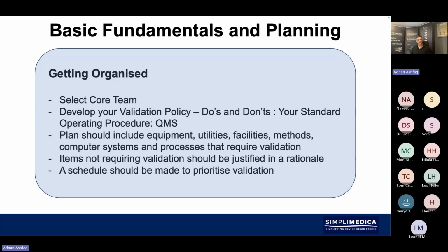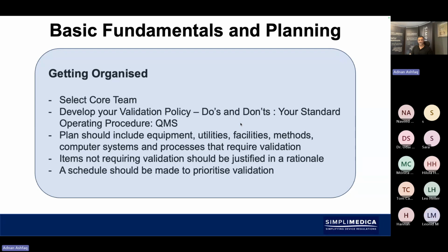How do you control the parameters and what parameters? What's the acceptance criteria? There have been occasions where I've had some vendors or clients tweaking the parameters as they're going along. This is very hard to validate because the whole premise of validation is that you have parameters predetermined and they're set throughout the validation, and you don't touch those parameters, and then your validation is based on those parameters.